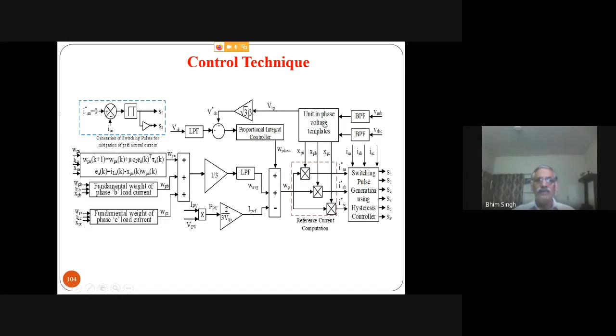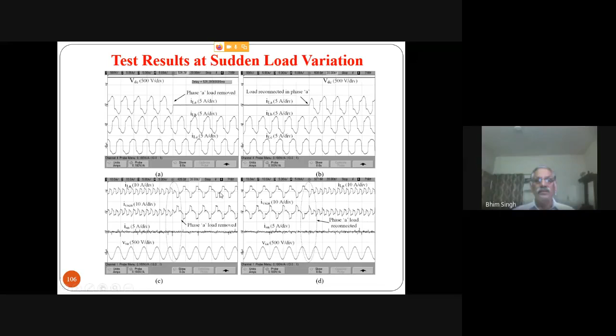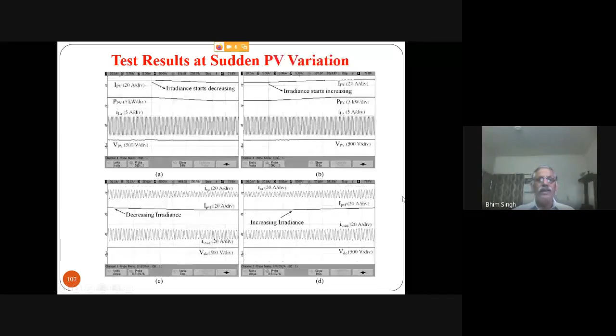Here also we change the DC link reference voltage so that it is related to the amplitude of the supply voltage, so that we reduce the losses in the inverter here too. That feature we also put in along with the feed forward term. So these are the modifications among our own findings, even for the active filter also, and you can see when load is removed or load is applied, the converter current and the neutral current are changing, but the grid neutral current is 0. That's where the neutral current compensation comes in.